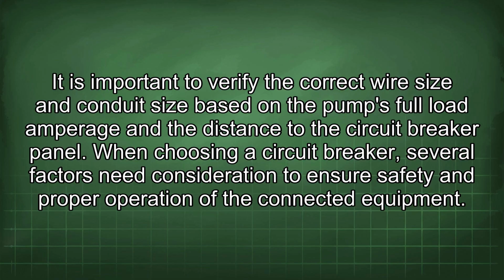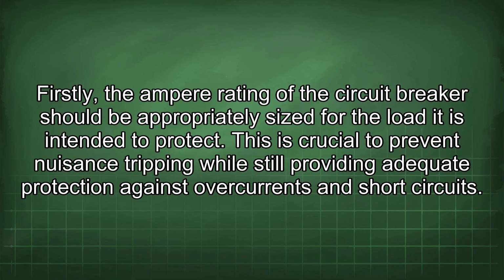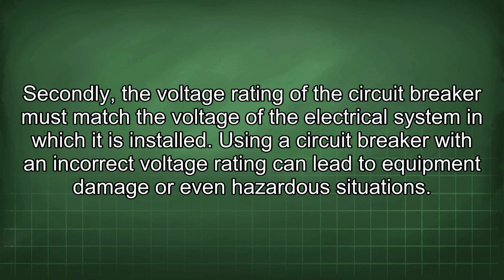When choosing a circuit breaker, several factors need consideration to ensure safety and proper operation of the connected equipment. Firstly, the ampere rating of the circuit breaker should be appropriately sized for the load it is intended to protect. This is crucial to prevent nuisance tripping while still providing adequate protection against overcurrents and short circuits. Secondly, the voltage rating of the circuit breaker must match the voltage of the electrical system in which it is installed. Using a circuit breaker with an incorrect voltage rating can lead to equipment damage or even hazardous situations.